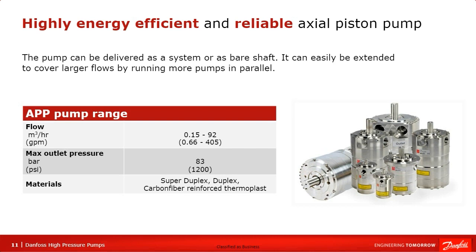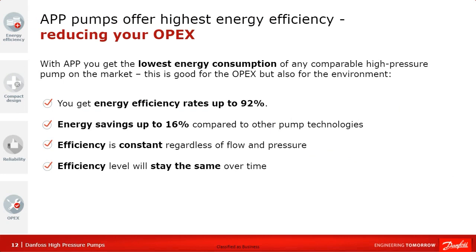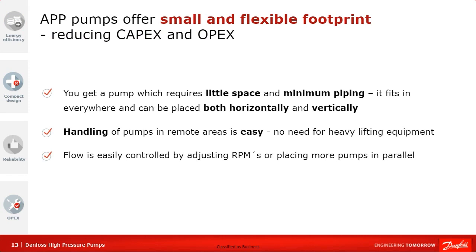The beauty of positive displacement pumps is that they are very efficient, which impacts OPEX for users — these pumps have the lowest energy consumption, resulting in significant savings compared to other technologies. With APP pumps you get efficiency rates up to 92%, which is up to 16% better than other pump technologies on the market. Positive displacement pumps control their flow through the RPMs of the motors, and the efficiency is constant regardless of what RPMs you operate at — you get proportional flow versus RPMs from the pump.